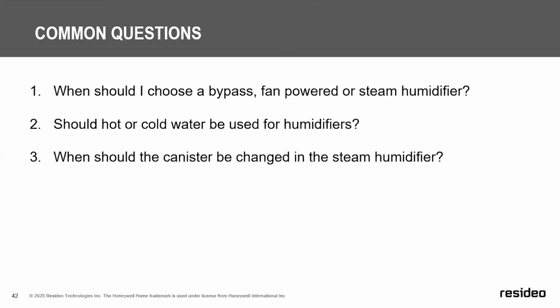So should hot or cold water be used for humidifiers? Well, I'm going to add a little more to that question. Let's begin with cold water, which is really probably the standard choice and the only choice for steam. We don't want to add hot water to steam humidifiers because it can throw off, oh darn it, I'm losing the word, Jamie. It can throw off the diagnostics that the humidifier uses to manage the water in the cylinder. It also changes the temperature of the water, which affects how the unit drains during its drain cycle.